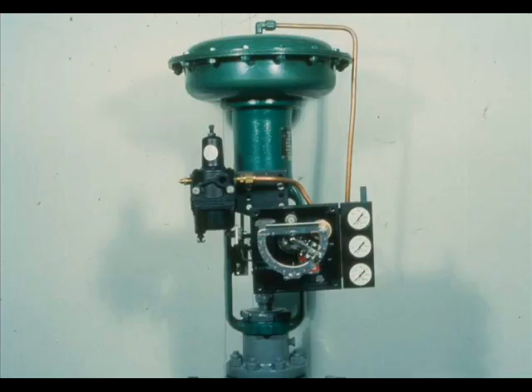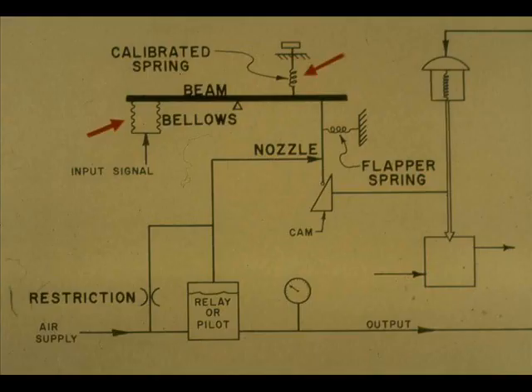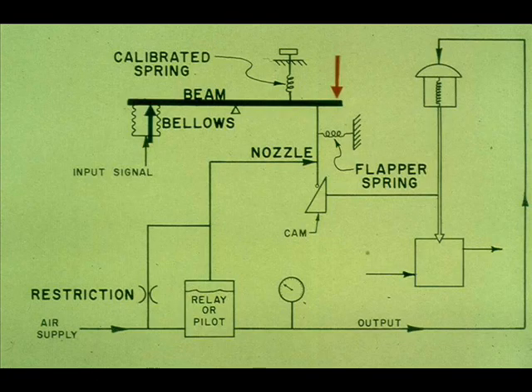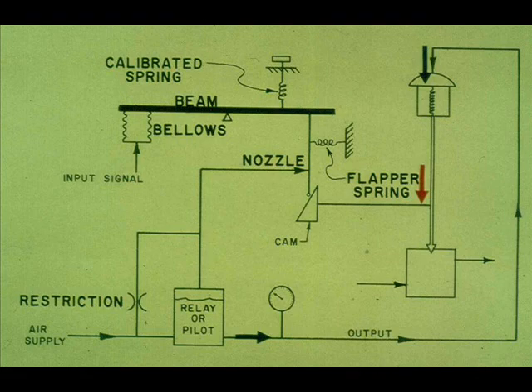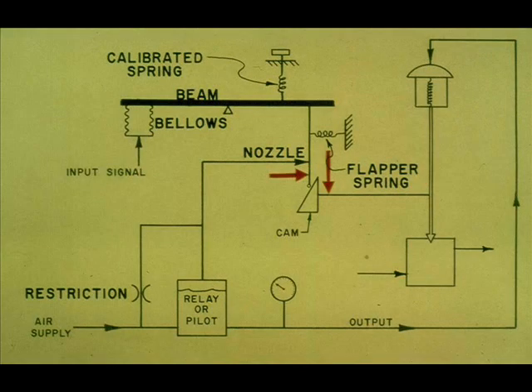In the motion balance positioner, the valve stem movement acts through directly connected mechanical mechanisms to restore a flapper nozzle relationship. The force created by the pressure in the input bellows is opposed by a calibrated spring. An increase in signal pressure in the bellows causes the right end of the beam to move downward. This causes the flapper to slide along the cam and cover the nozzle. Increased output air pressure from the relay causes the valve stem to move downward.